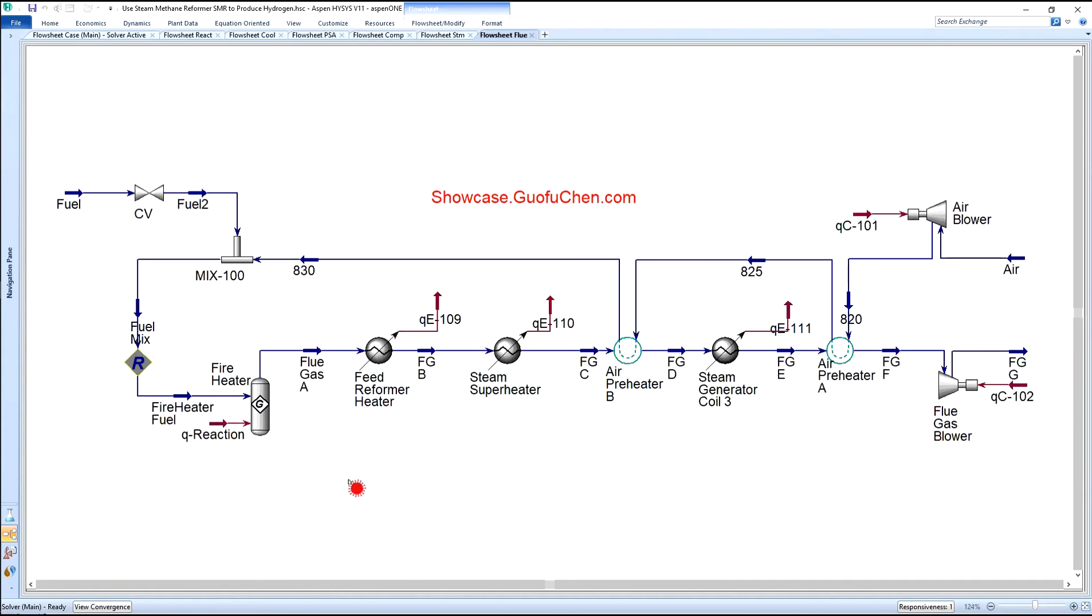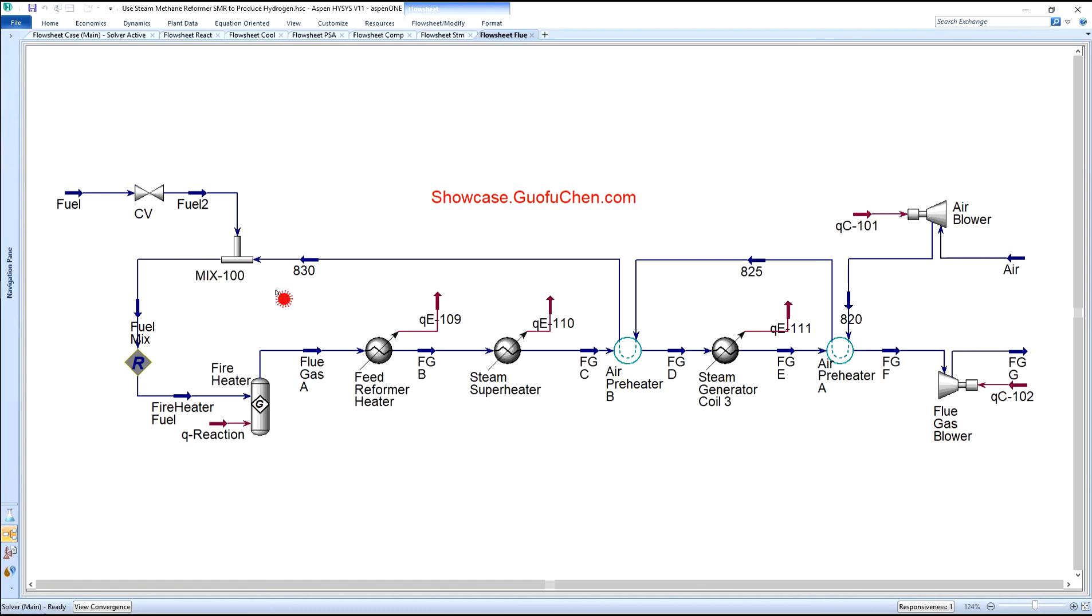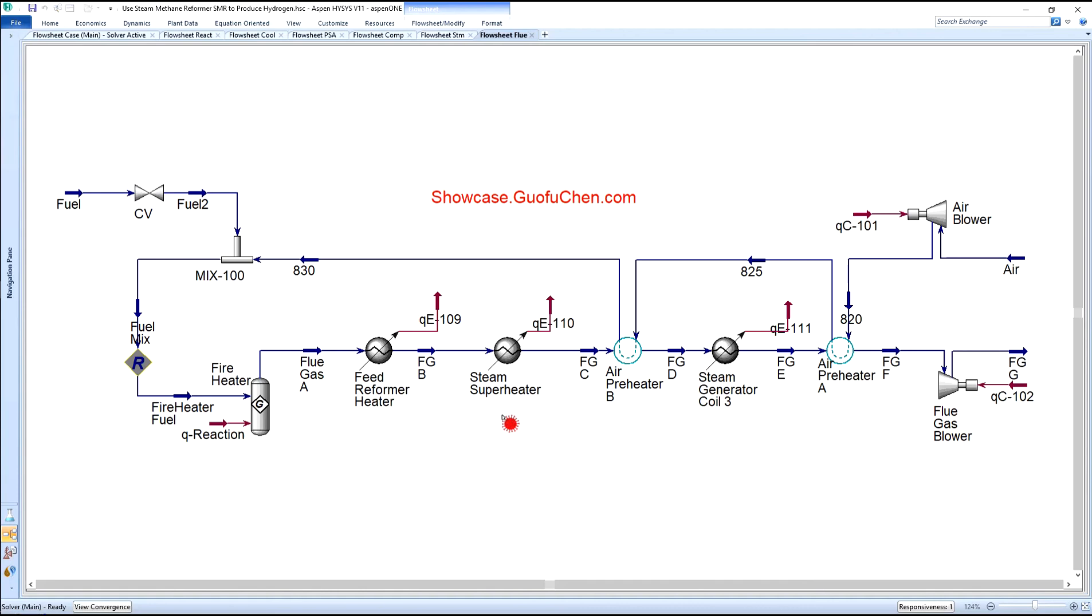The last module of the six is the flue gas module. The fuel gas and the preheated air are burned in the fired heater to provide the heat for reformer reaction. Then it is cooled down in a series of heat exchangers. The flue gas is first used to preheat the steam methane mixture before entering the reformer. Then it is used to superheat steam, preheat air, generate steam, and preheat air again before being vented to the atmosphere through a blower.